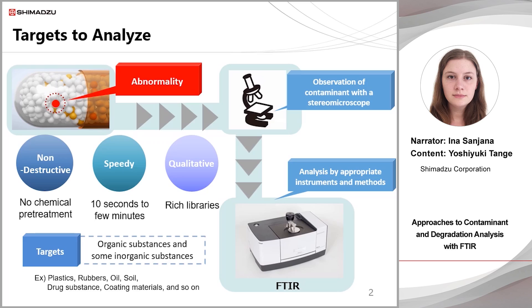For FTIR, no chemical pretreatment is required. The measurement is completed in a short time frame, from 10 seconds to a few minutes. In general, qualitative analysis using spectra requires specialized knowledge, but analysis is aided by libraries with many spectra stored in them. Both organic substances and some inorganic substances can be measured using FTIR.